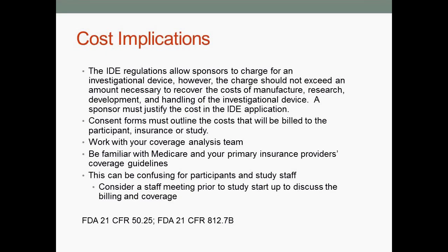There are many other cost implications, and so we talked about the devices and the IDE regulations. Like I said, sponsors are allowed to charge for the device, and so you have to really understand what the price is and what's involved in it. So sponsors need to be able to justify the cost. They can recover the cost of manufacture, research development, or handling the investigational device. And they actually have to provide a justification to the FDA for why they've come up with this cost.